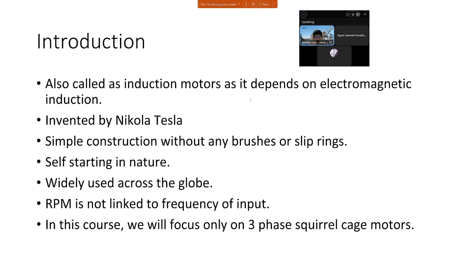It was invented by the great Nikola Tesla. The construction is very simple, and there are no brushes or slip rings. And that is one of the best advantages, because the number of components that are wearing down and need to be replaced or maintained are decreasing. It is self-starting in nature, whereas some motors are not. Like if you have a one-phase asynchronous motor, that is not self-starting; you have to give it some mechanical input to start it. It's very widely used because of its simplicity and cost-effective nature.